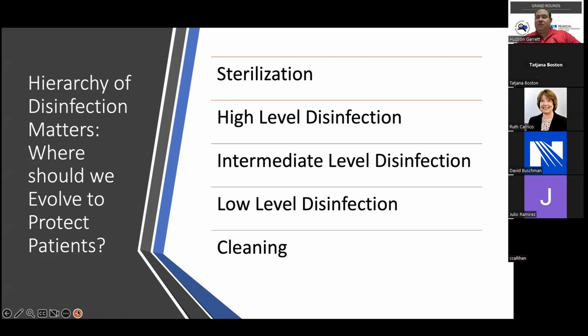Unfortunately, we still don't have a lot on the U.S. market that is capable of undergoing routine sterilization multiple times without degradation. So that's where we're starting to see a movement toward single-use devices. Keep in mind single-use devices can come in lots of different forms, so it's important to get the manufacturer's instructions for use prior to utilization.